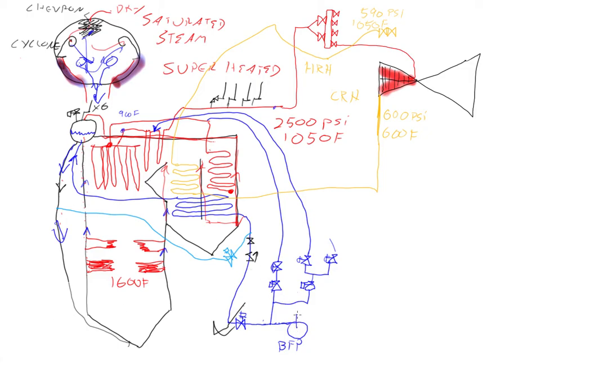So we come off the boiler feed pump and we go through control valves and we spray into the cold reheat. This is not tapping off of the discharge side of the boiler feed pump. The discharge side of the feed pump is about 3,000 psi at full load. This feed pump has several stages to take the pressure up from about 300 pounds off the DA up to that 3,000 pounds. So at an intermediate stage we have a scoop that steals some of that water at a lower pressure, so now we're only at 1,000 pounds.